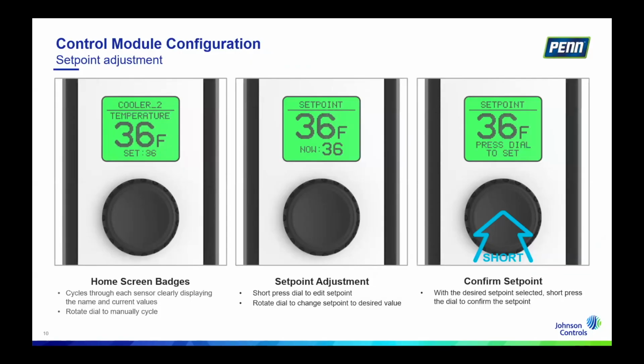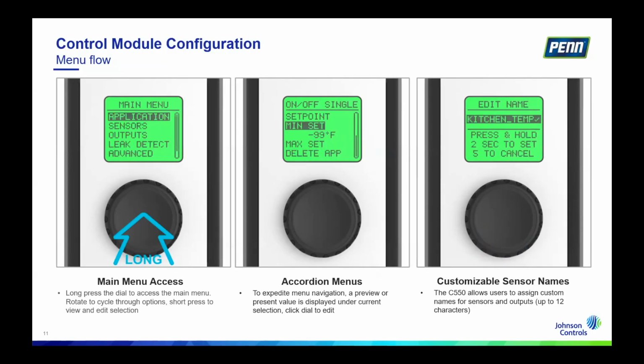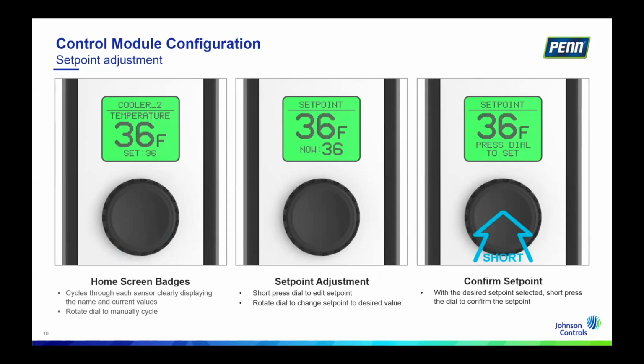Telling you a little bit about how the controller and the display is designed. We've simplified the user interface here, and you'll see that in the next slide, but I'll just go over it. So what we have here is what we call badges. That's what's displayed. The control is configured so every so many seconds it's going to show the next badge. But here, if we rotate this rotary dial, if there's another sensor hooked up, it'll show you what that sensor value is, and the set point. And if there are other warnings or alerts on the home screen, those will show in these badges.